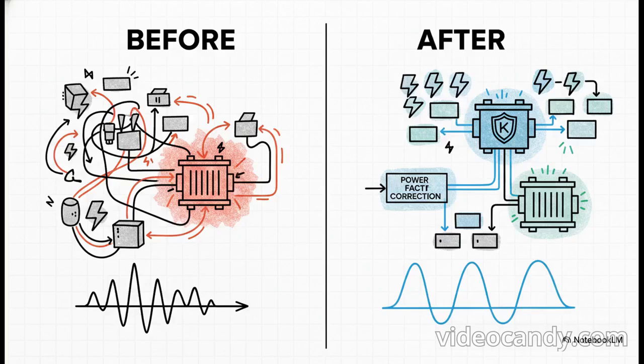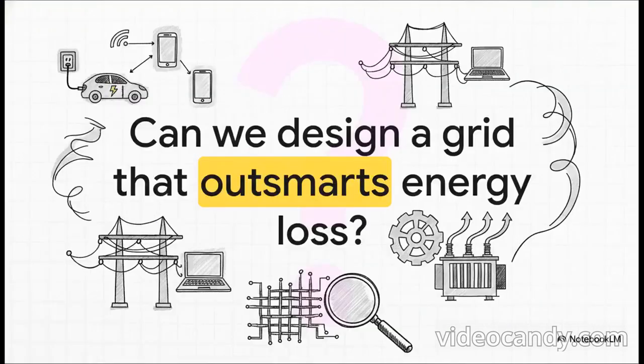And this is how we fight back against that energy drain. By understanding all these different factors, engineers can design much smarter systems. They can do things like segregate those dirty, nonlinear loads onto their own dedicated K-rated transformers. They can install equipment to improve the power factor, which lowers the overall current and cuts down on those copper losses. It's a whole strategy, a multifaceted approach to minimizing waste.